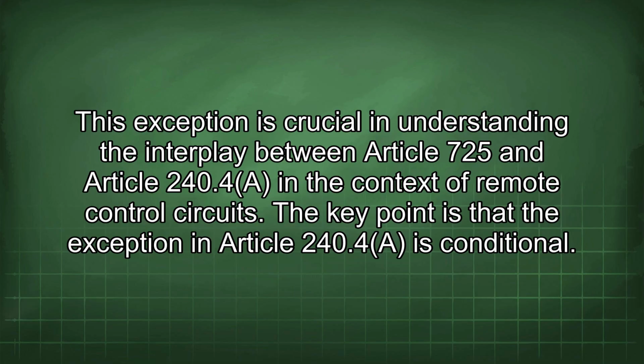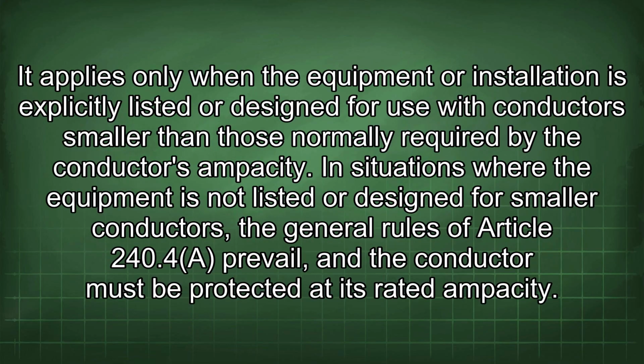This exception is crucial in understanding the interplay between Article 725 and Article 240.4 in the context of remote control circuits. The key point is that the exception in Article 240.4 is conditional. It applies only when the equipment or installation is explicitly listed or designed for use with conductors smaller than those normally required by the conductor's ampacity. In situations where the equipment is not listed or designed for smaller conductors, the general rules of Article 240.4 prevail, and the conductor must be protected at its rated ampacity.